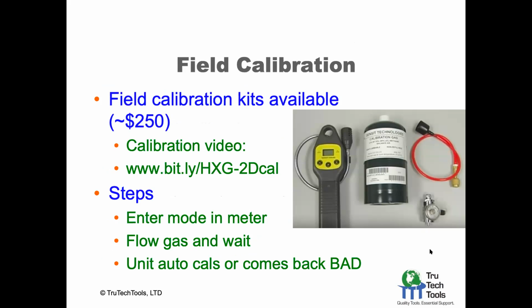So the field calibration kits are pretty simple. It's calibration gas, which looks like a can of propane but is actually calibration gas to a specific level, a regulator to flow the gas, a cap to put over the sensor, and a fitting to attach it to the tank. And there's actually a calibration video. Again, you get a copy of these slides if you want to go look at that. Just to review, not to train you in calibration here, you enter a specific mode in the meter that's indicated in the instruction manual. You flow the gas from the calibration tank, wait for a response, and either the unit auto-calibrates or it comes back bad. So there's a lot of automation built into it. They made it pretty simple to calibrate.